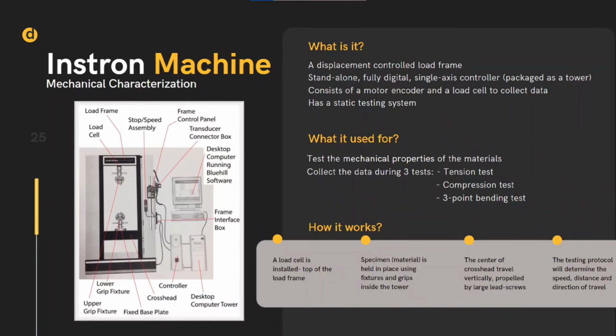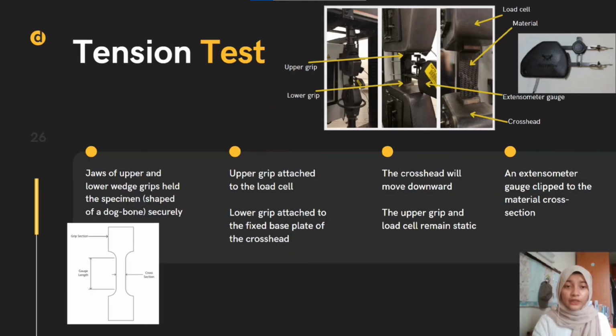So how does this test machine work? First, a load cell is installed at the top of the load frame, and a specimen, which is the test material, is held in place using a fixture and grip inside the instron tower. Once a testing protocol has been initiated, the center crosshead will travel vertically, propelled by large lead screws located inside the columns. The testing protocol, which has been programmed by the operator beforehand, will determine the speed, distance, and direction of the travel. This is the first test from the instron machine, which is the tension test.